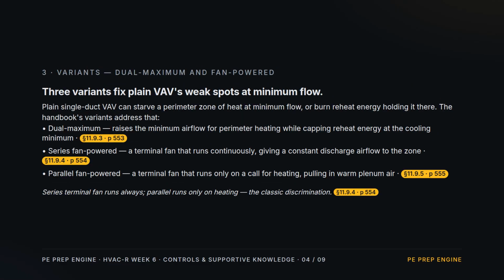Variants. Plain single-duct VAV can starve a perimeter zone of heat at minimum flow, or burn reheat energy holding it there. Three Handbook variants fix that. Dual maximum raises the minimum airflow for perimeter heating, while capping reheat energy at the cooling minimum. Series fan-powered adds a terminal fan that runs continuously, giving a constant discharge airflow. Parallel fan-powered adds a terminal fan that runs only on a call for heating, pulling in warm plenum air. The exam point. The series fan runs always, the parallel fan only on heating.